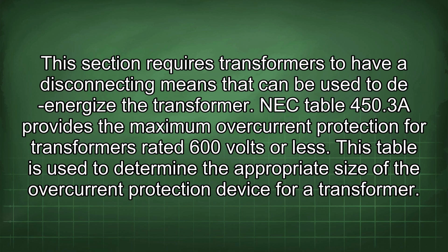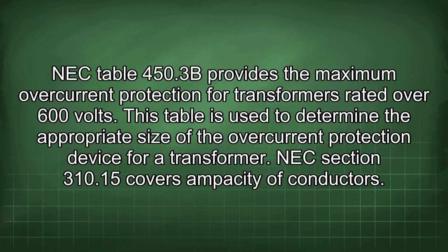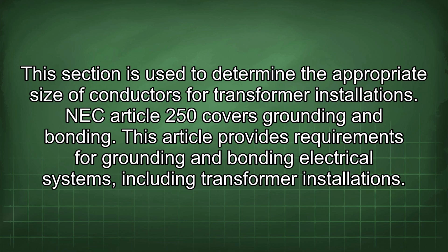NEC Table 450.3A provides the maximum overcurrent protection for transformers rated 600 volts or less. This table is used to determine the appropriate size of the overcurrent protection device for a transformer. NEC Table 450.3b provides the maximum overcurrent protection for transformers rated over 600 volts. This table is used to determine the appropriate size of the overcurrent protection device for a transformer. NEC Section 310.15 covers ampacity of conductors. This section is used to determine the appropriate size of conductors for transformer installations.